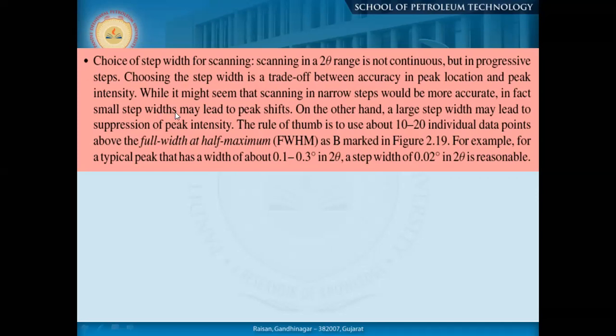These are the most important parts. Whenever you go for any analysis, even on our solar instrument, they will ask what desired accuracy you want, from which angle to which angle, and what step size you want for your sample. Once you know it, you can fill in the form properly. A large step width may lead to suppression of peak intensity, and this is the problem with our data also.